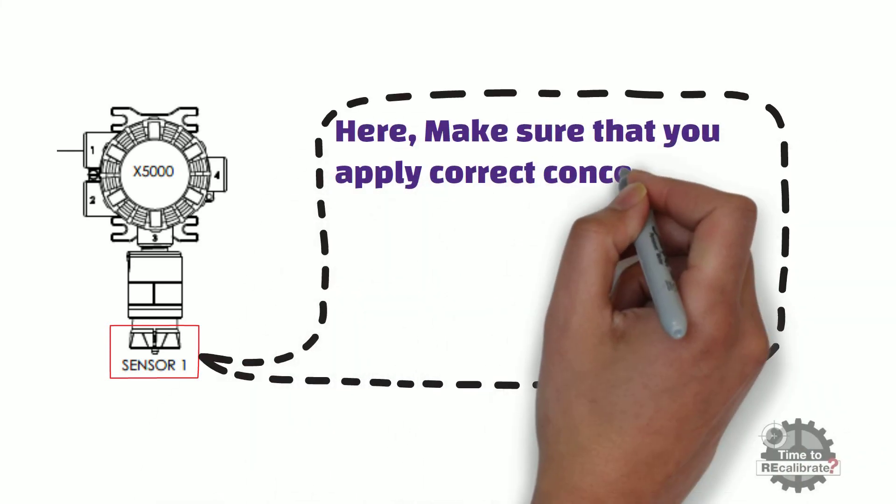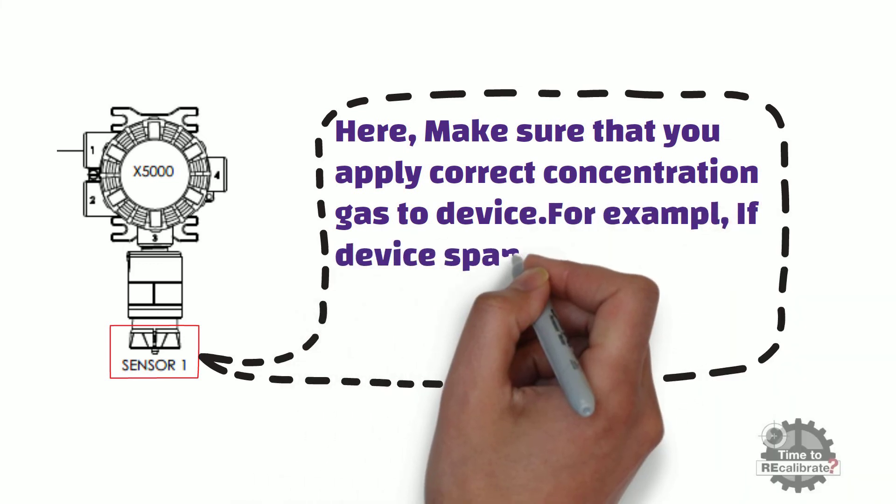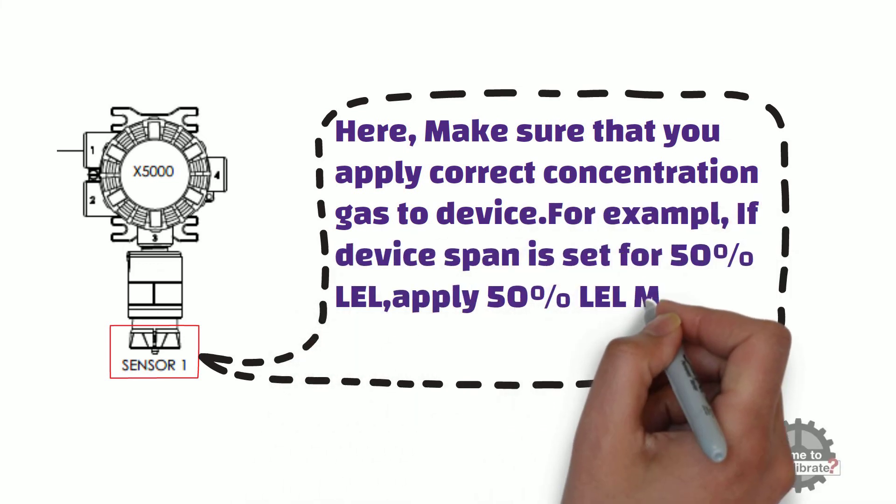For example, if device span is set for 50% lower explosion limit, apply 50% lower explosion limit methane gas to the sensor.